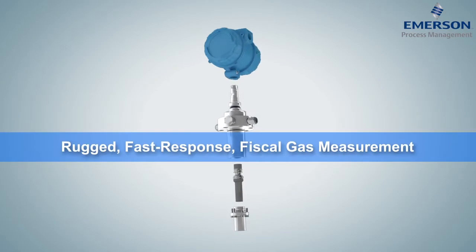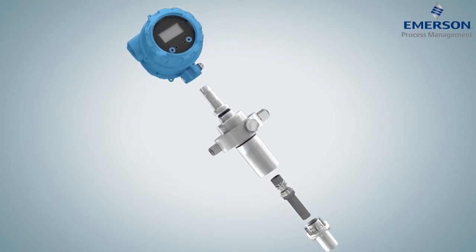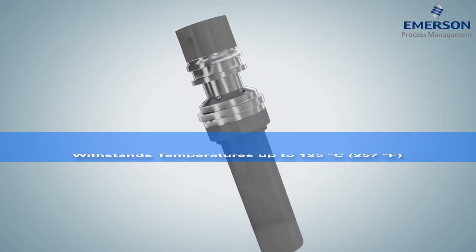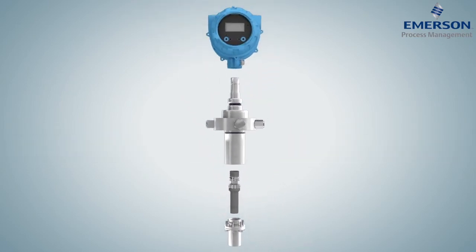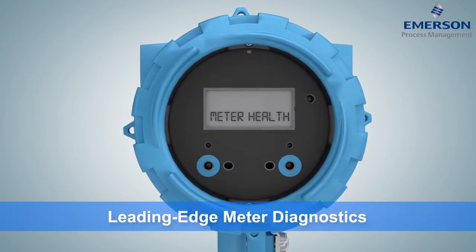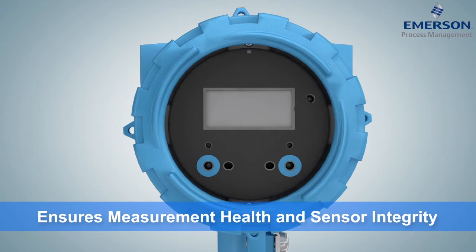Our rugged, fast-response Gas Density Meter, or GDM, is designed to measure high-value products like natural gas, fuel gas, and hydrogen to international fiscal and custody transfer standards. Able to withstand temperatures up to 125 degrees Celsius and pressures up to 250 bar, the GDM's vibrating cylinder technology can be configured for a wide range of applications and comes with full backwards compatibility of form and fit. Like all of Micro Motion's new density and viscosity meters, the GDM's internal diagnostics ensure measurement health and verify sensor integrity.